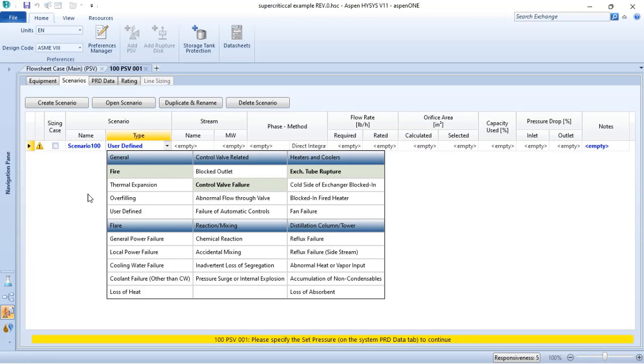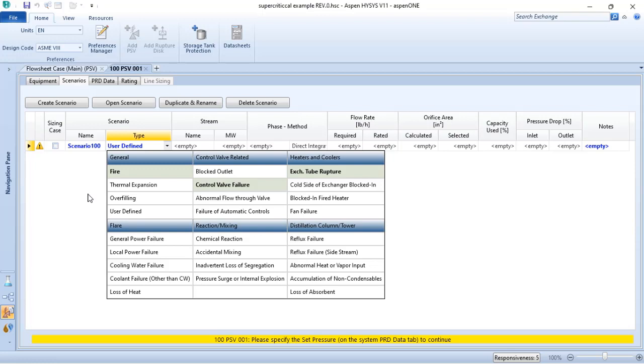So here you can see that, for instance, fire is a scenario where you can have overpressurization of your system because if you keep adding heat to a vessel, the fluid inside the vessel will expand and with that increase the pressure until it reaches the maximum allowable working pressure of the equipment, or you relieve the amount of fluid inside to prevent the overpressurization.